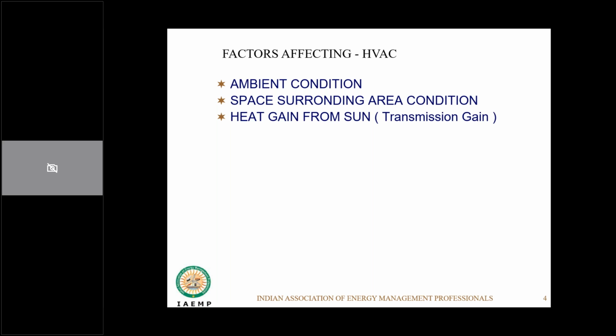Heat gain from the sun. The major part of the air conditioning load is the heat gain from the sun. If you look at residential or office premises per se, this forms almost 60 to 70% of your air conditioning heat gain, and it has to be factored in properly to have an effective HVAC design.